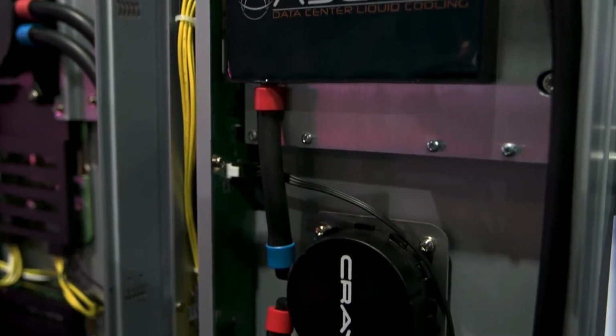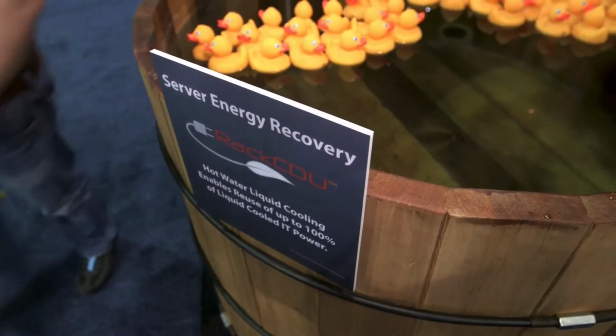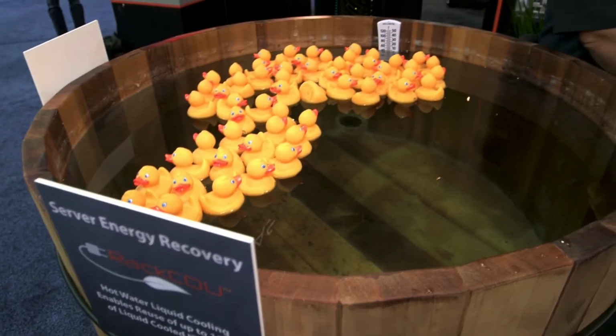So, Steve, with these highly dense systems in data centers today, that's where liquid cooling really does what it does best, isn't it? Correct. In fact, behind me here we have a 36 kilowatt rack that we're direct-to-chip liquid cooling. We're bringing 35C water in to cool that, so we're cooling it with hot water. We're taking 20 kilowatts of that out of the rack. We're actually bringing it up and over, warming up the hot tub to keep our ducks comfortable. That hot tub is currently at about 119 degrees Fahrenheit. Then we're taking the water back, the additional heat up, and rejecting any of it that remains with a dry cooler. The advantage is we're not doing any compressive cooling, and compressive cooling is what drives up your cost. Right, so you got those compressors, crunching the freon and all that electricity. Exactly. Here, this is just a simple fan and a radiator on the roof.